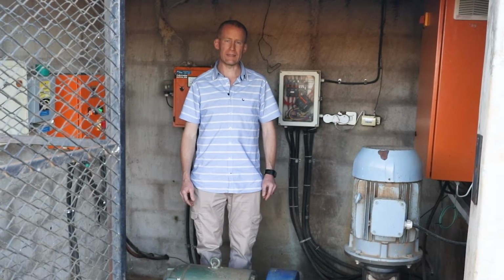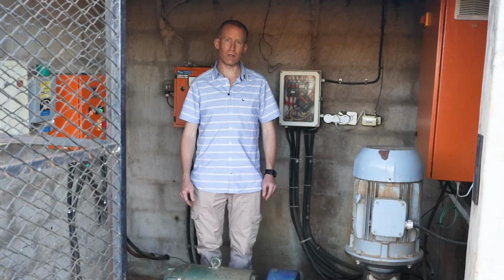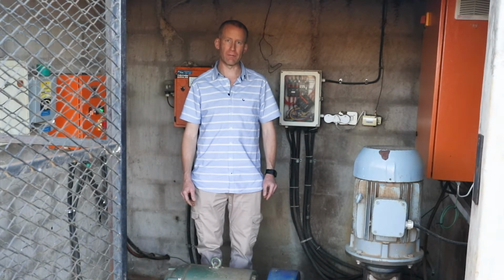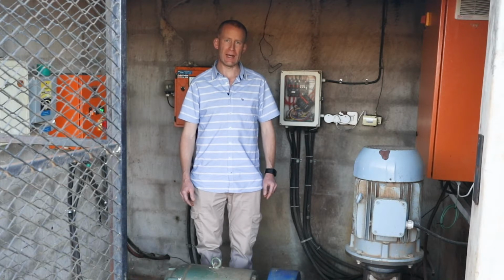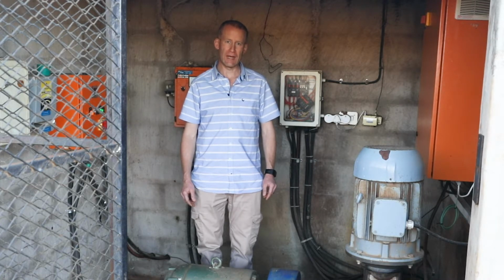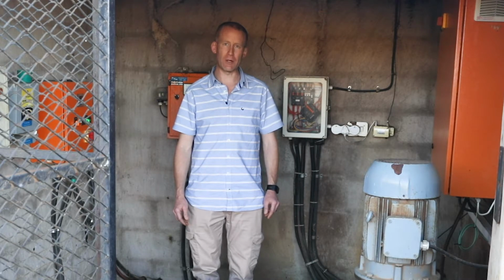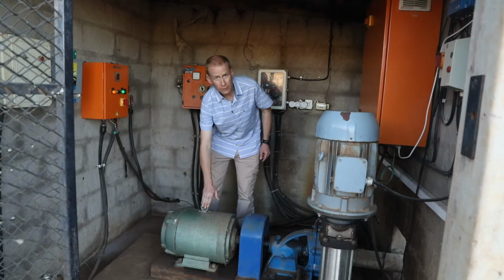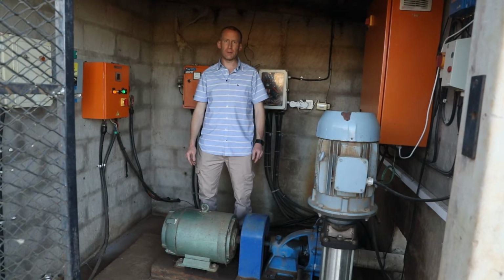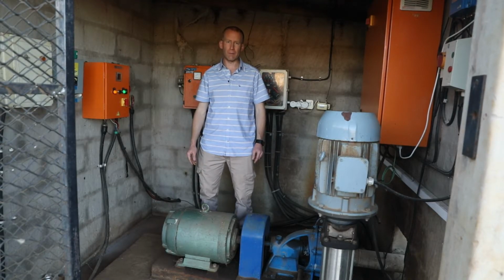Our client was highly skeptical that a 9 kilowatt pump and motor would be able to deliver the same flow rate and pressure as the original 30 kilowatt unit. That's why you see both systems are still plumbed in, so that if we were wrong in our predictions, the client could go back to the original pump and motor. Luckily, this proved to be unnecessary, and the 9 kilowatt pump and motor delivers more than enough flow rate and pressure for the Pivot.